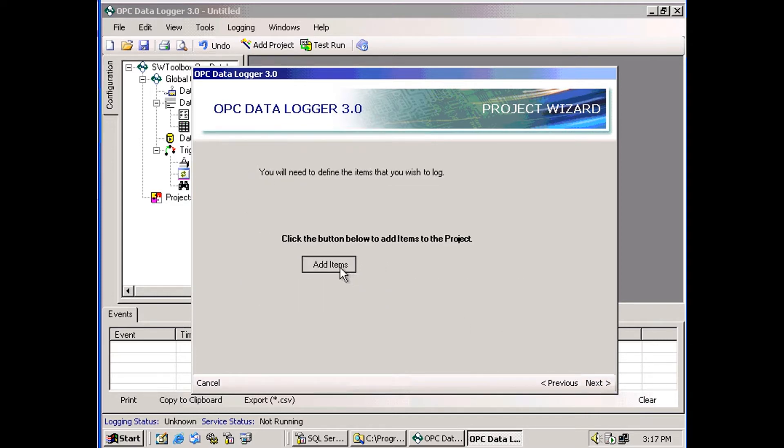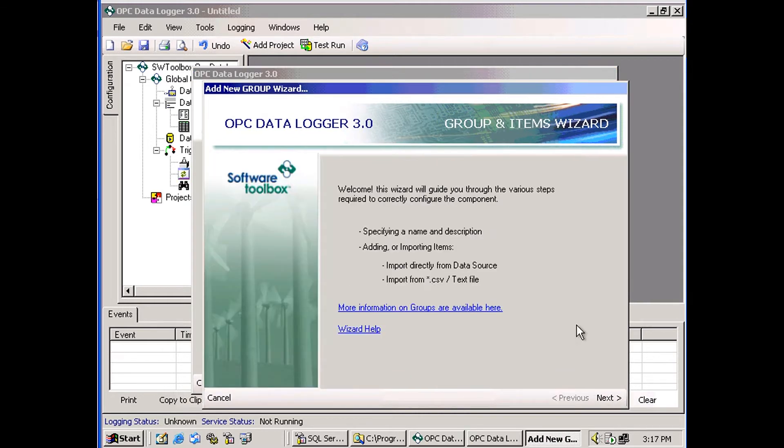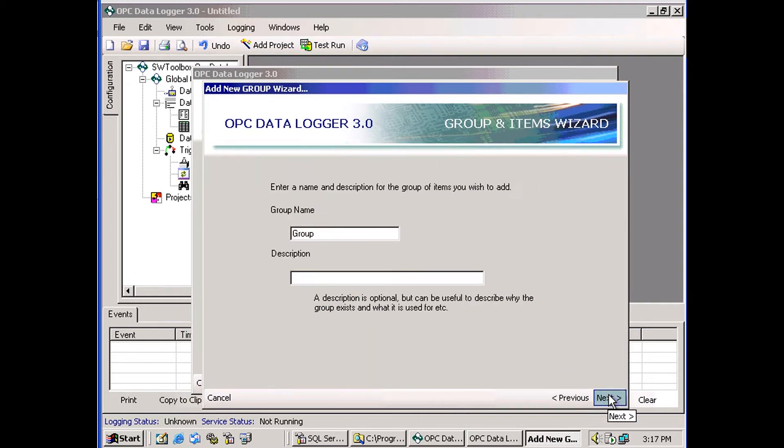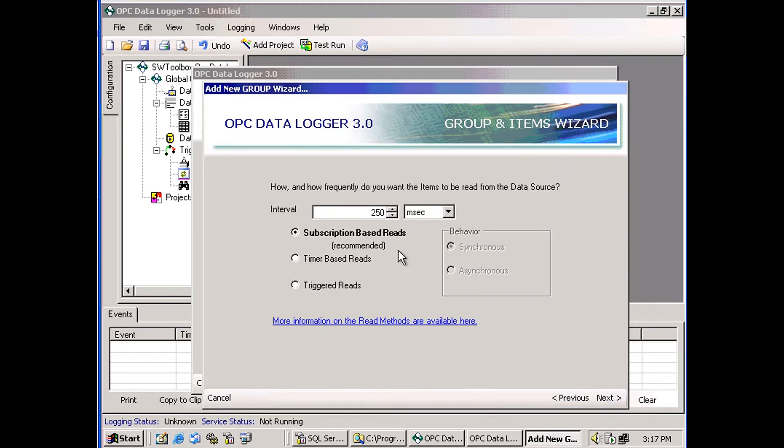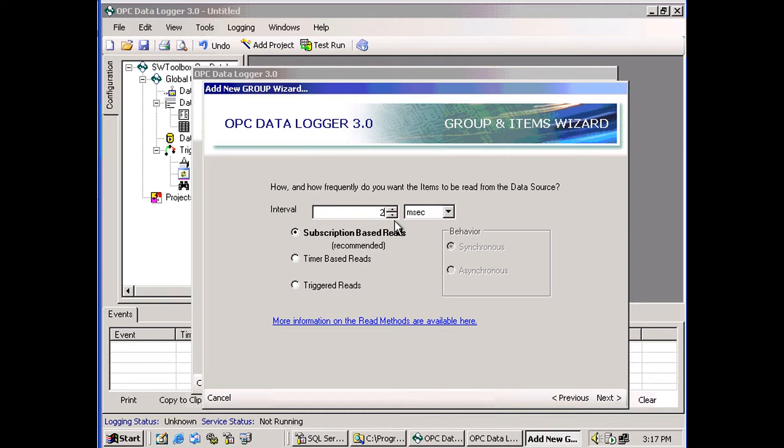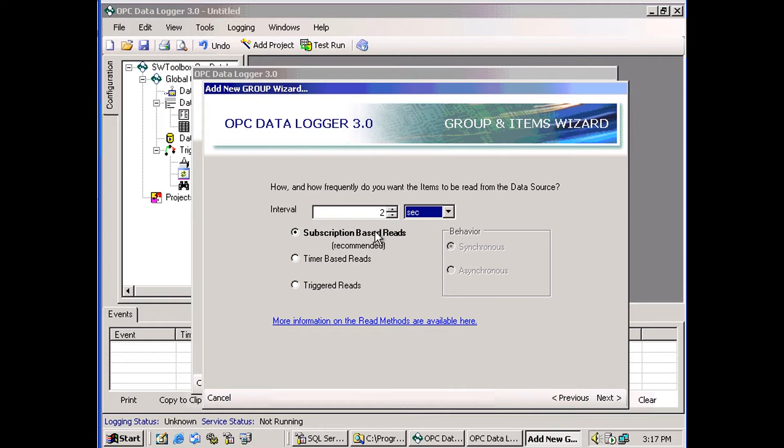So now we can add groups, which we do by clicking this Add Items button. You can change the name of the group. I'm going to leave it as Group. Here you can choose how the items are going to be read from the server. I'm going to use Subscriptions with an interval of 2 seconds. This means that the server is going to poll the device every 2 seconds and any time there's updates, it's going to send a message to the data logger. Then the data logger is going to log those values to my database.